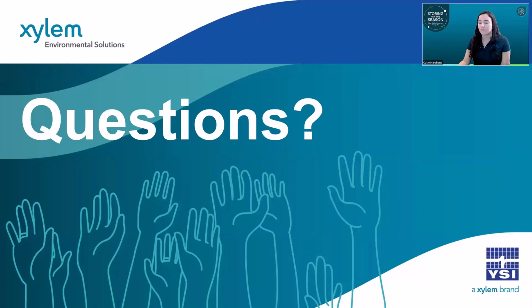There was a question about if you're removing the sensors, should you always cover or plug the bulkhead? I would say yes, just to prevent anything from getting into those ports: dust, debris, any liquids that you don't want in there. So if you have port covers, I would plug those up anytime you don't have a sensor in the port. Our instruments ship with a few port plugs that you can use, and if you need more, you can also purchase more.